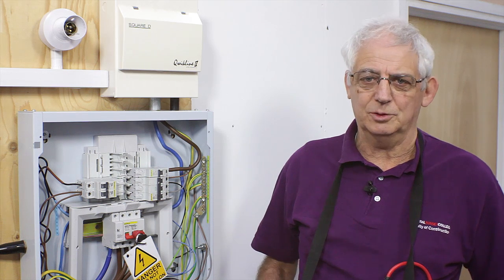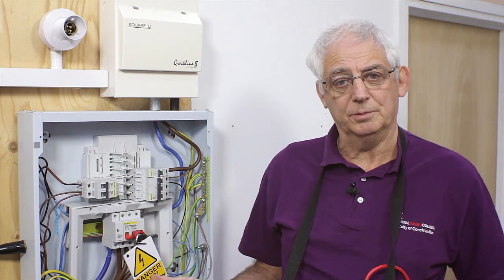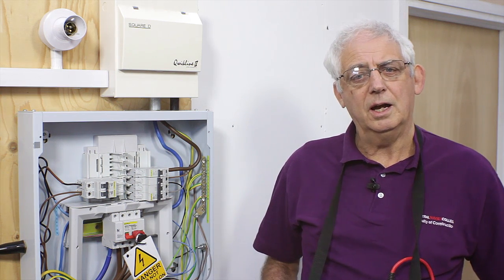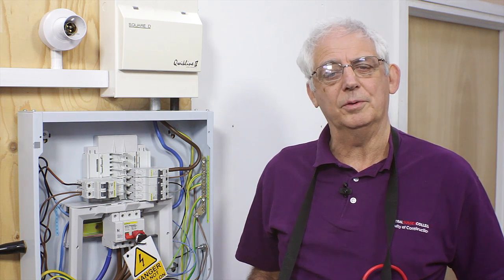Before we start, we need to make sure that anything that could be damaged by the test voltage is disconnected, isolated or bypassed. Any dimmer switches are bypassed, lamps removed if possible. Just those sort of precautions for two reasons. One, we don't want to damage the equipment, and two, it will give us false readings anyway, and we'll be looking for a fault that may not be there.